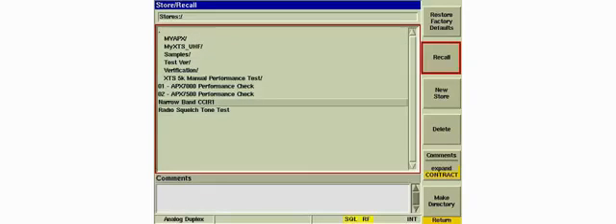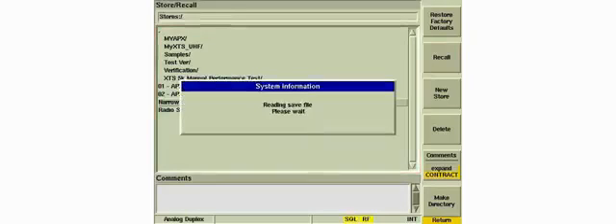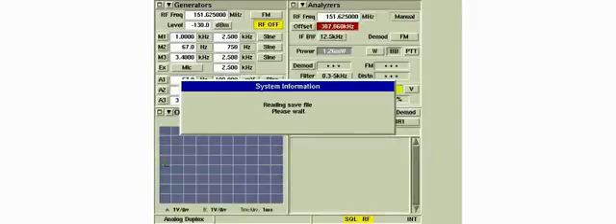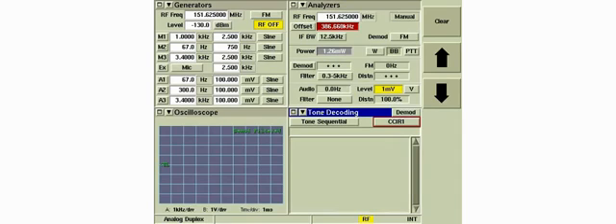Double clicking on the entry with a mouse or pressing the Recall soft key while it is selected will recall the stored settings. All of the parameters for the test are recalled.